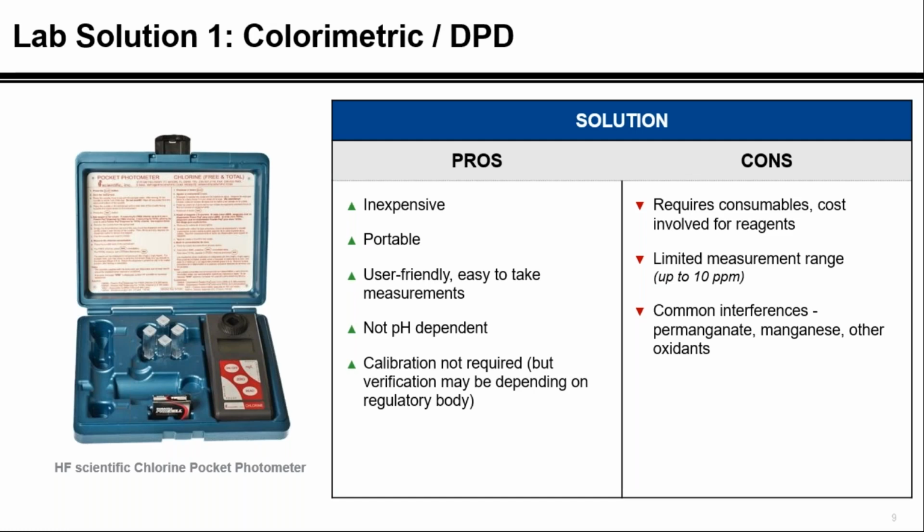Before you take the measurement, we want to wipe the cell outside clean with a lint-free cloth or a chem wipe, and ensure that you put the cell into the instrument the same way each time. There's not really a correct way to put it in unless you do have a scratch or something that you want to avoid being the light measurement path. But we want to put it in the same way when we zero and when we read, so that we're sure that if there is any abnormality in the glass, we're zeroing that out. And obviously, for any optical measurement, we want to make sure that we're not touching the sides of the sample cell before measurement and putting in fingerprints that can also cause issues with that.